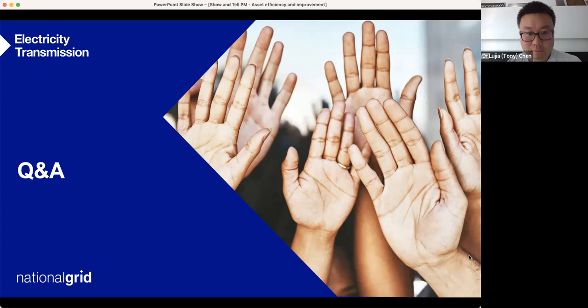Yeah. Thank you, Tony. So I have a question from Rob Walden here. Do you have any telemetry that tells you that there is a leak or that a leak is developing? And does this data get sent OTA to a monitoring center? I'm not sure it's that sophisticated. I've been to substations where it is literally hand recorded on a whiteboard how many kilograms of SF6 are topped up. Generally, all these substations that have the equipment will have low pressure monitoring alarms. That will trigger, and then the operator needs to top up the SF6. And by regulatory requirements, because this is a very potent greenhouse gas, you have to record how much you top up. So that's generally the situation at the moment.